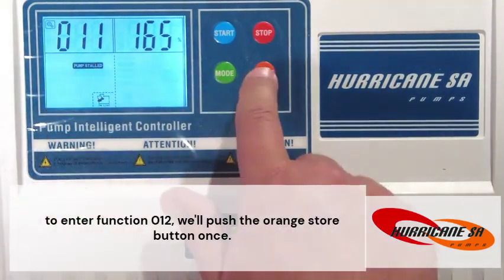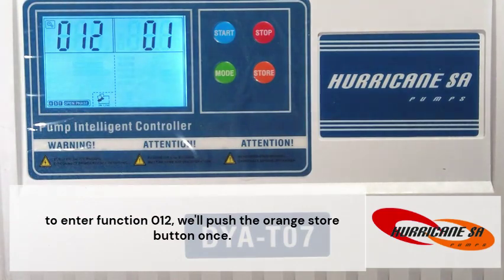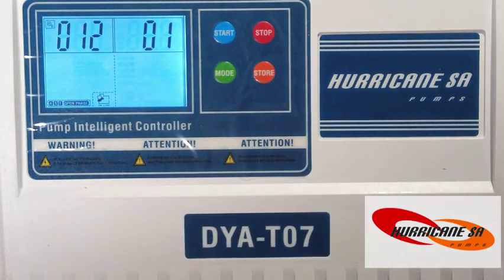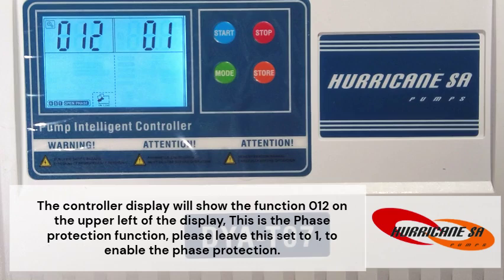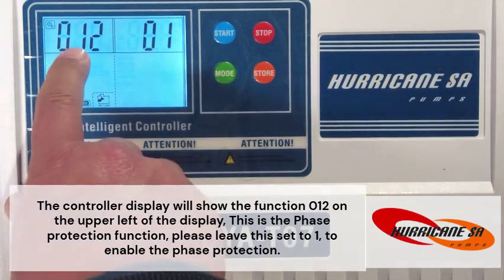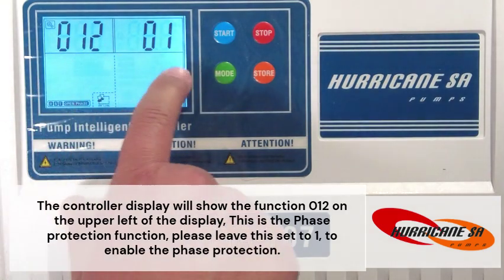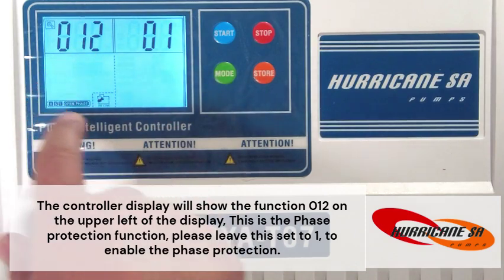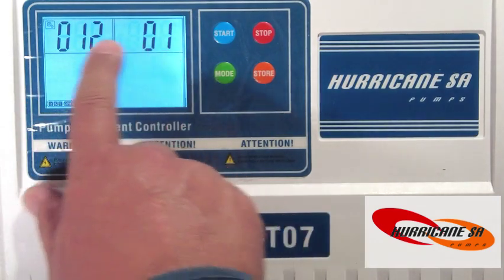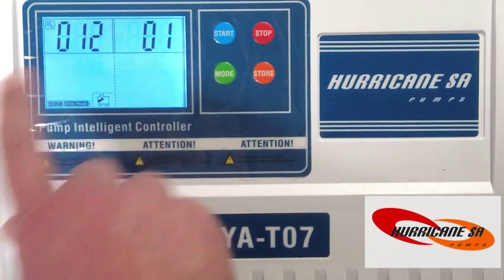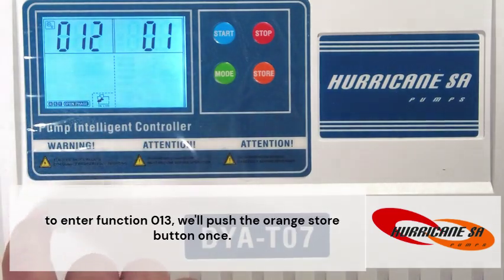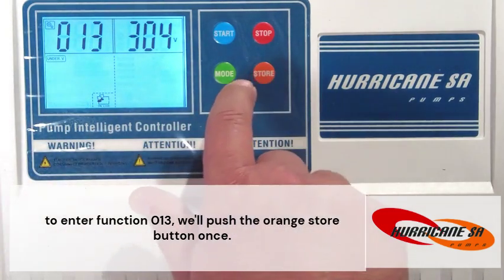To enter function 012, we'll push the orange store button once. The controller display will show the function 012 on the upper left of the display. This is a phase protection function. Please leave this set to 1 to enable the phase protection. To enter function 013, we'll push the orange store button once.